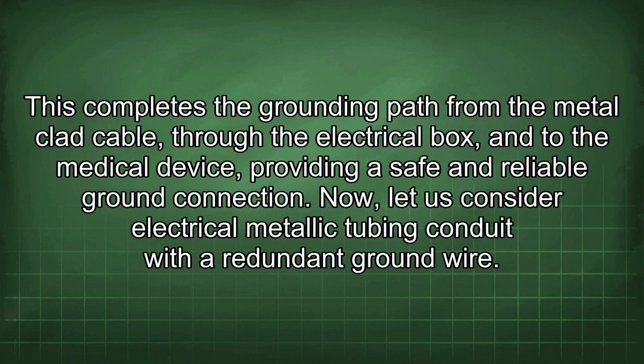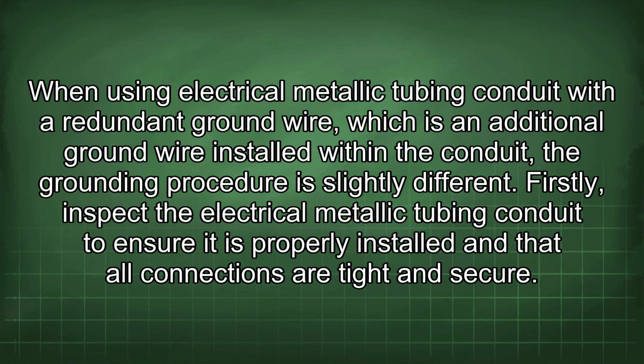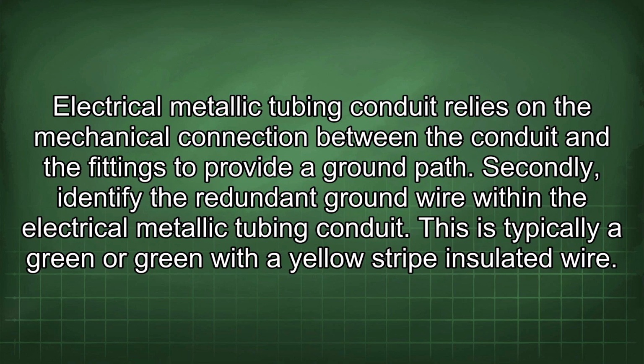Now let us consider electrical metallic tubing conduit with a redundant ground wire. When using electrical metallic tubing conduit with a redundant ground wire, which is an additional ground wire installed within a conduit, the grounding procedure is slightly different. Firstly, inspect the electrical metallic tubing conduit to ensure it is properly installed and that all connections are tight and secure. Electrical metallic tubing conduit relies on the mechanical connection between the conduit and the fittings to provide a ground path.